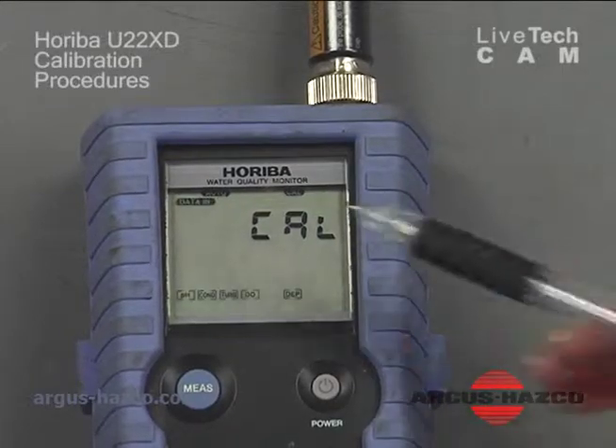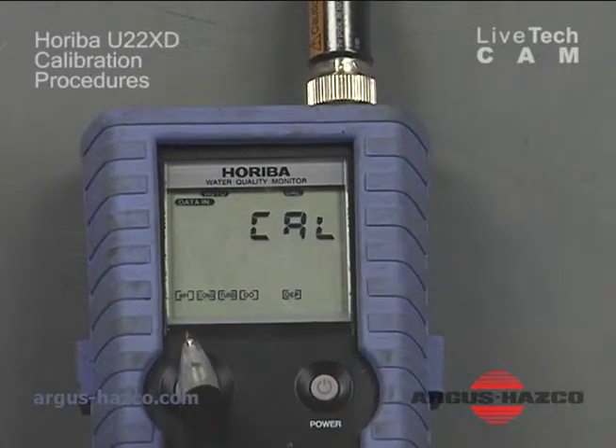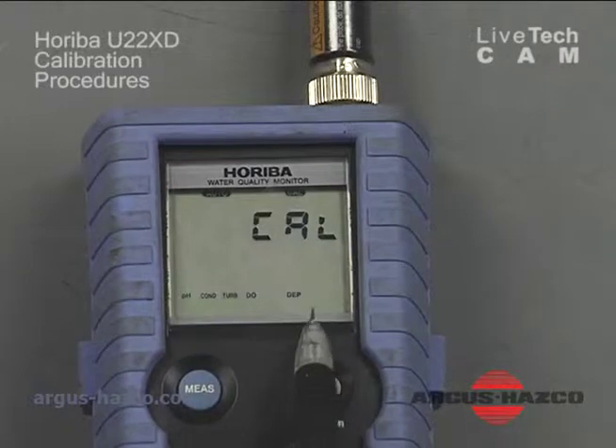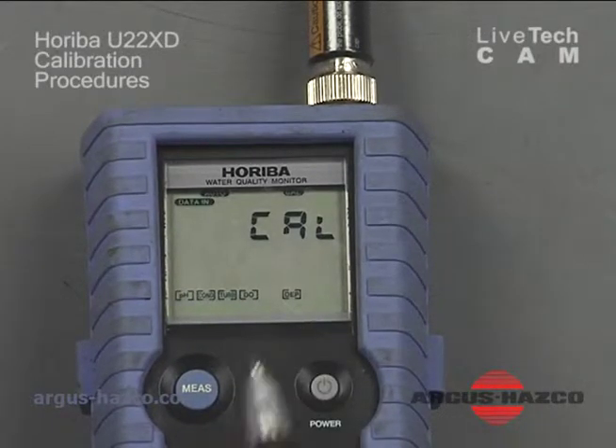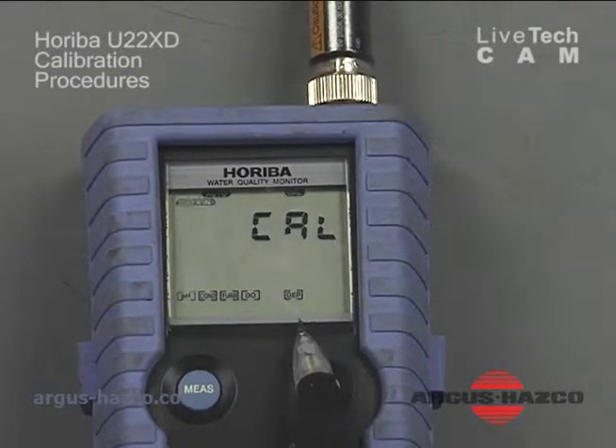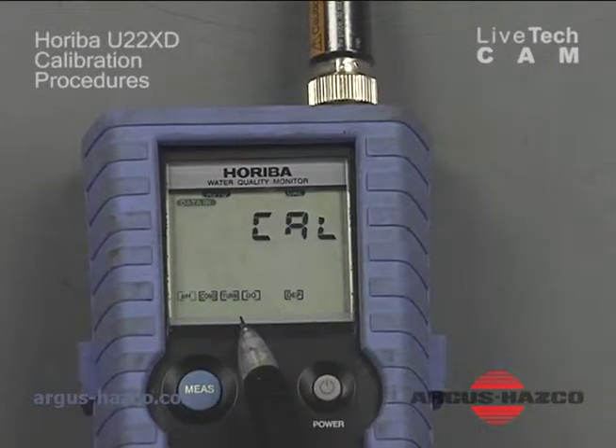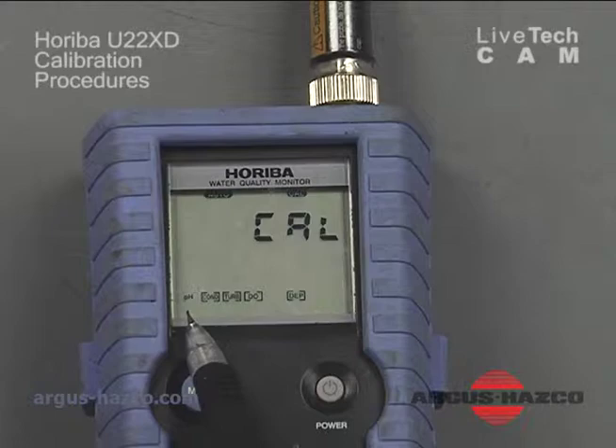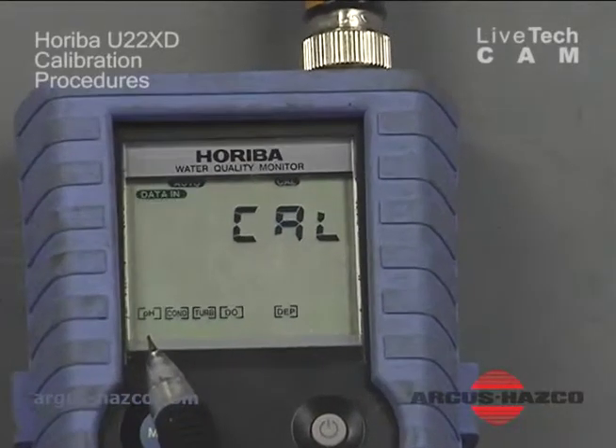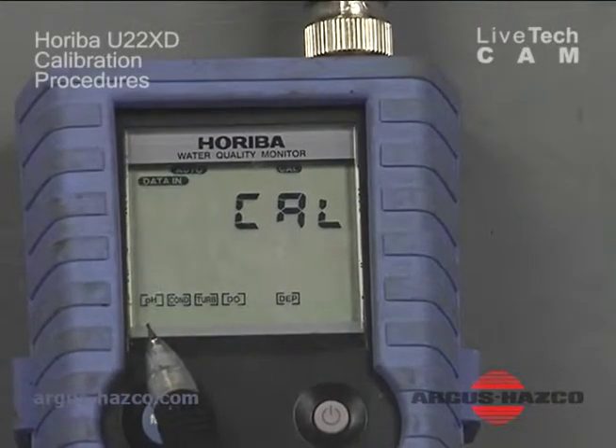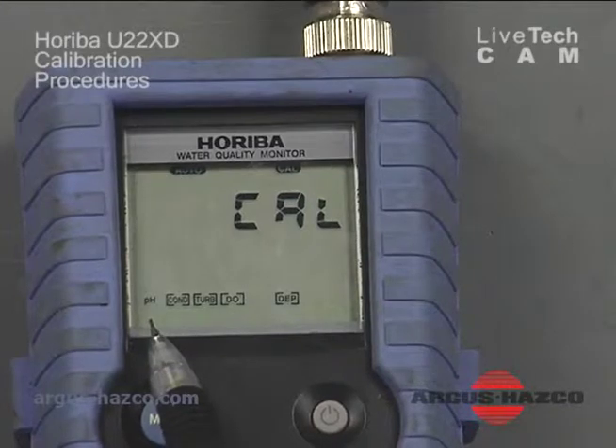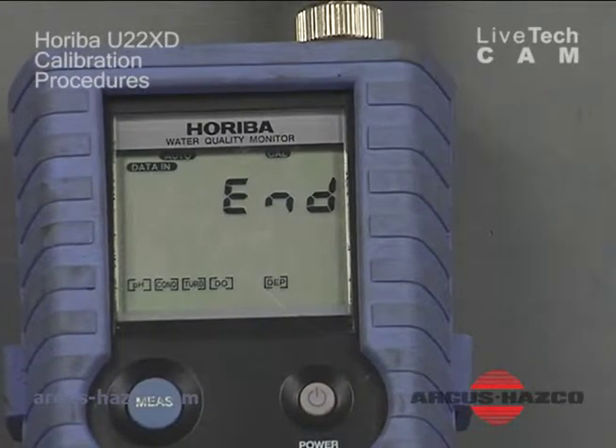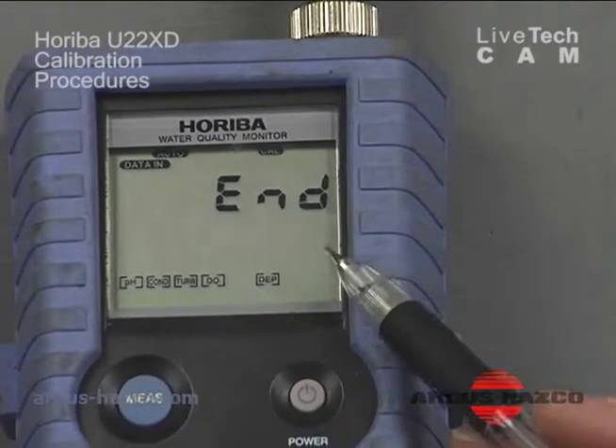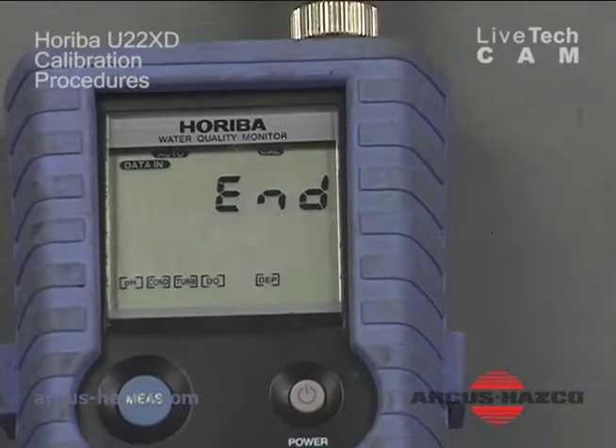And as I'm calibrating, it'll say data in, and all my different parameters that I'm calibrating will flash. As each parameter calibrates, the bracket will stop flashing when it's calibrated. Right now we're calibrating our pH right now. That's the last parameter to calibrate. And once it's done calibrating, it says end on our display.